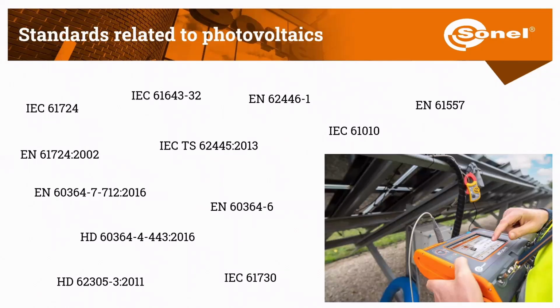What is important from our side, as a manufacturer of electric measurement equipment, is to comply with several norms. Some of the norms are related with the measurement unit, and some are related with the safety of measurements on the exact installation. For example, norm EN 61557 is related with the safety of electric measurement equipment. However, norm 62446-1 is related with photovoltaic installation. So to comply with everything, a user or potential customer has to comply with most of the norms that are stated here.